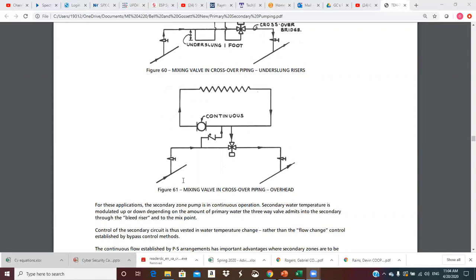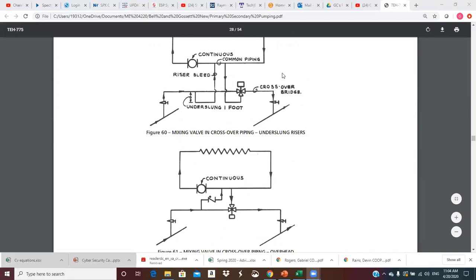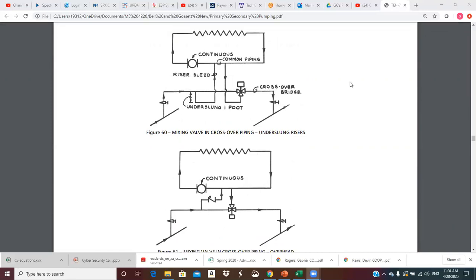The secondary zone pump is in continuous operation. Secondary water temperature is modulated up or down depending on the amount of primary water the three-way valve admits into the secondary through the bleed riser. However much we allow out through the crossover, that's how much goes into the secondary and adjusts the temperature. Control of the secondary circuit is thus vested in water temperature change rather than flow change control established by bypass control methods.